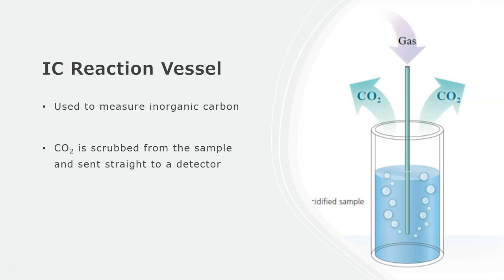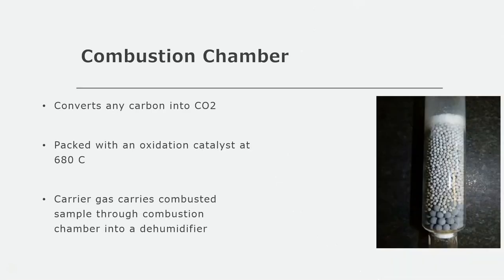Next up in the flow path comes the inorganic carbon or IC reaction vessel and the combustion chamber. The sample is sent to one or the other based on what you're trying to measure. In the IC reaction vessel, an acidified sample with gas will cause inorganic carbon to be purged as carbon dioxide, and this CO2 can then be measured by the detector. Once your sample has been properly diluted, acidified, and maybe sparged or measured for inorganic carbon, it will be injected into the combustion chamber. The combustion chamber is packed with an oxidation catalyst and it reaches a temperature of 680 degrees Celsius, and the carrier gas will carry your combusted sample through this chamber onto the next steps.